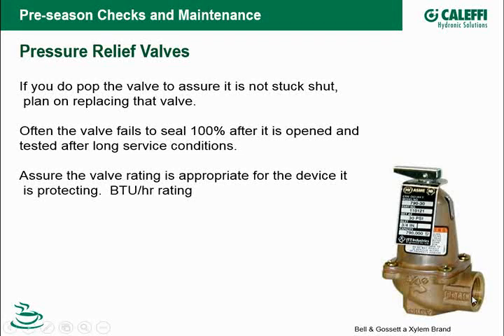Put a discharge tube on that is the other thing I would say. I can't tell you how many times I've been on a job where one of these is on top or on the side of a boiler, and it's just going to blow out all over the room if it discharges. There's a threaded connection there, and you should take that down within 6 inches of the floor so that if it does pop and discharge, it's going to go down to the floor, down to a floor drain.